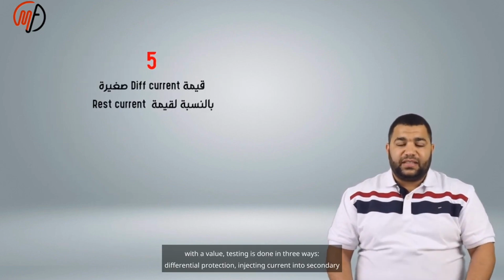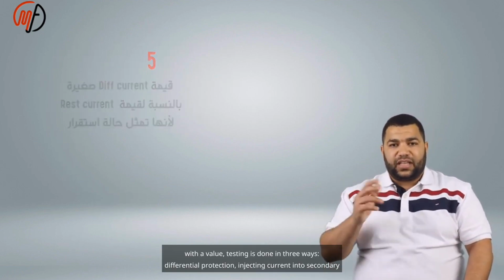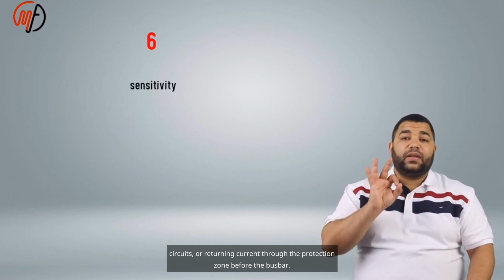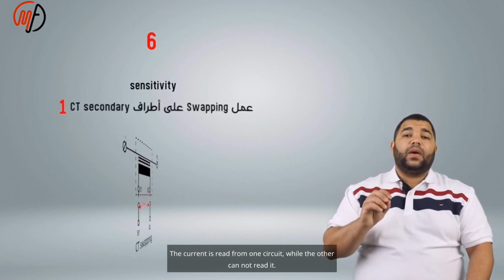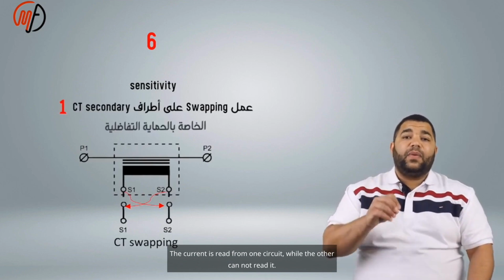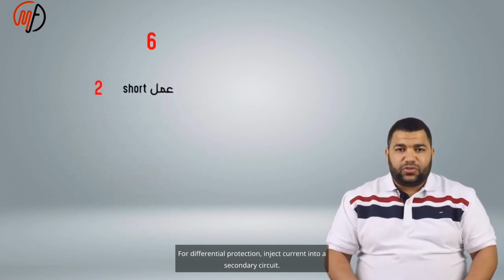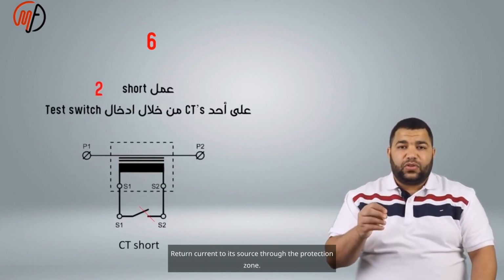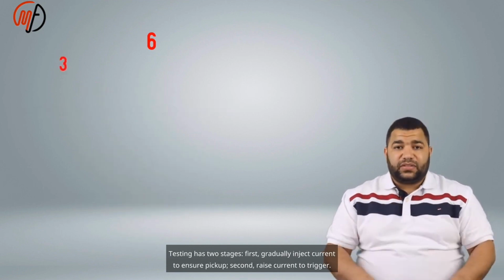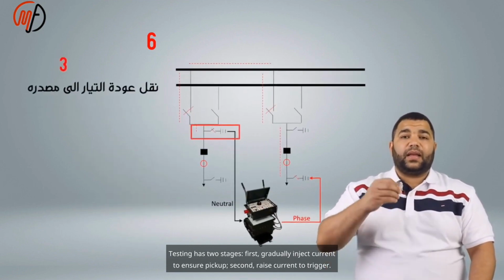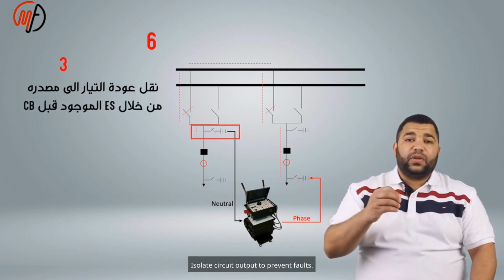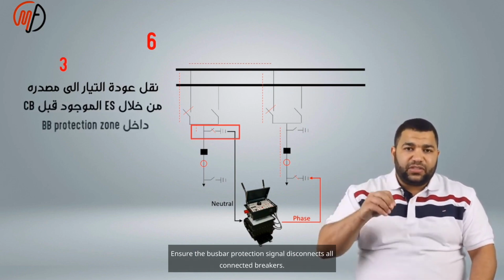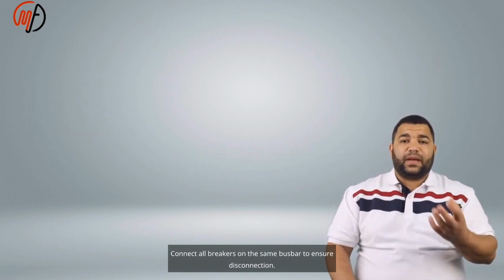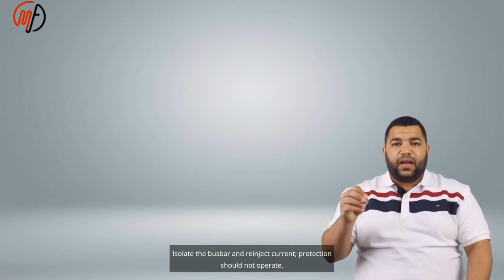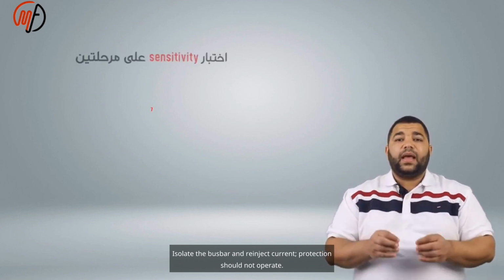With a small value, testing is done in three ways: differential protection, injecting current into secondary circuits, or returning current through the protection zone before the bus bar. The current is read from one circuit while the other cannot read it. For differential protection, inject current into a secondary circuit and return current to its source through the protection zone. Testing has two stages. First, gradually inject current to ensure pickup. Second, raise current to trigger. Isolate the circuit output to prevent faults. Ensure the bus bar protection signal disconnects all connected breakers. Distribute breakers across the bus bars. Connect all breakers on the same bus bar to ensure disconnection. Isolate the bus bar and re-inject current. Protection should not operate. Repeat the previous method.